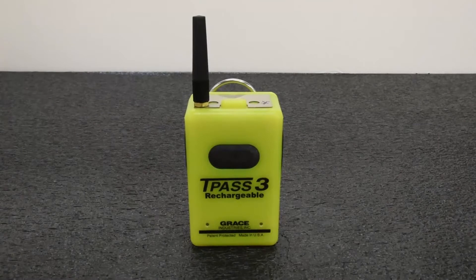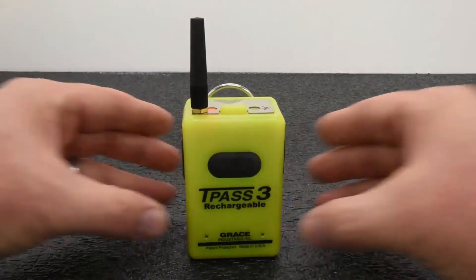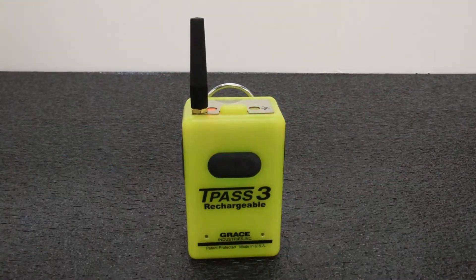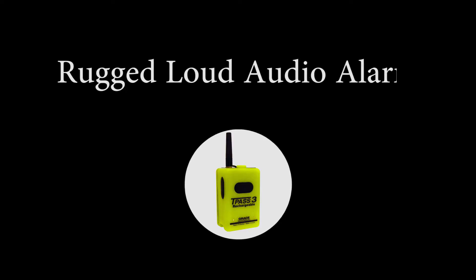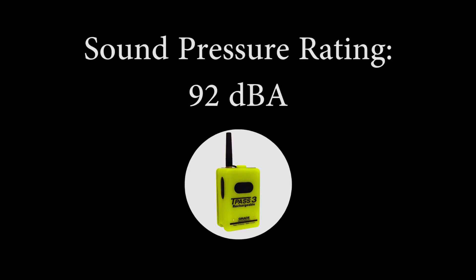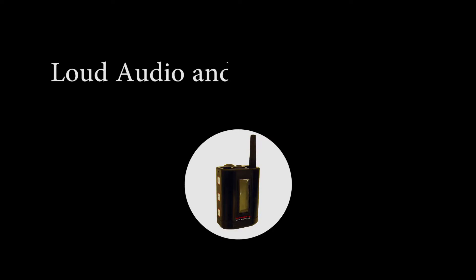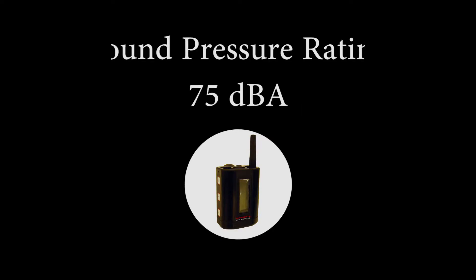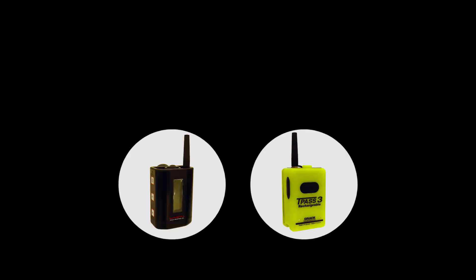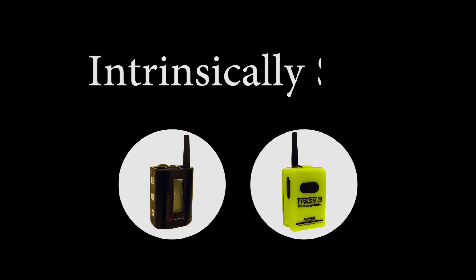In addition to motion alarm activation on the TPASS 3 and SC500, both devices have the ability to activate a manual panic alarm. The TPASS 3 has a very loud audio alarm with a sound pressure rating of 92 dBA. All SC500 models have a loud audio and vibration alarm with a sound pressure rating of 75 dBA. All models of the SC500 and TPASS 3 are intrinsically safe.